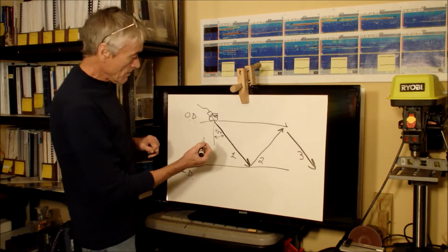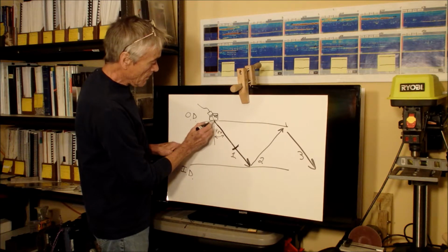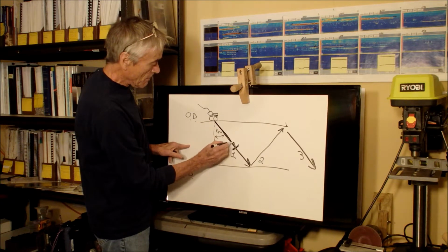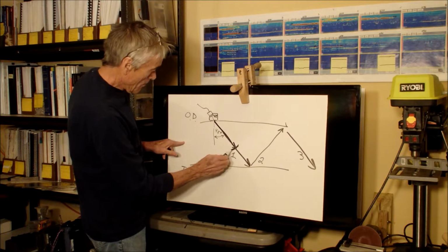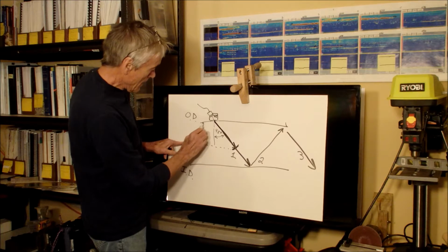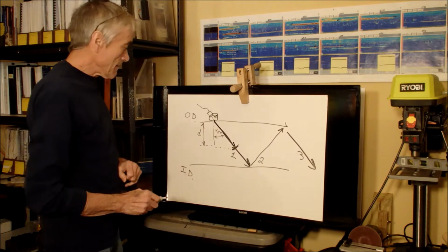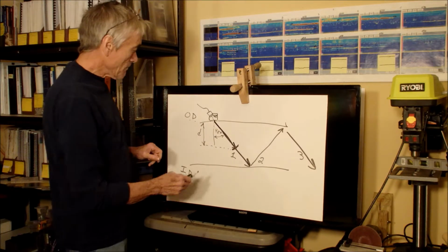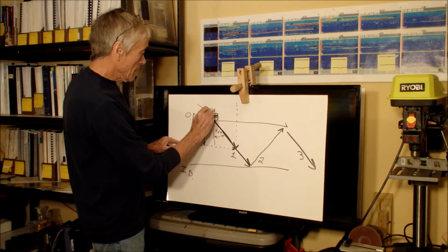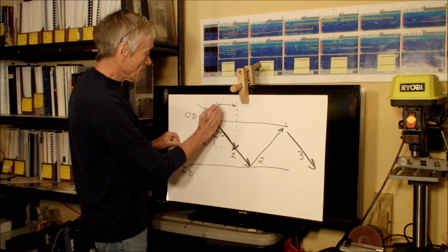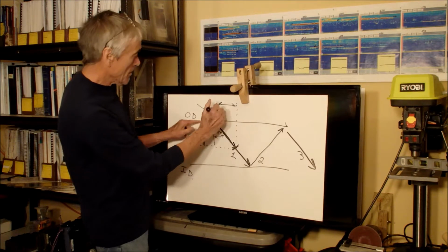Another thing we'll run into is, okay, say you had a reflector out here. Knowing the velocity of the sound, we can measure how much time it takes for the sound to go out to the reflector and come back. And knowing that, we could use trigonometry to calculate the depth. By the same token, we can use trigonometry to figure out what that surface distance is. This being the surface distance above the flaw from here to here.